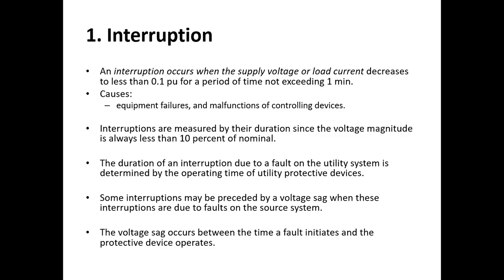Now the interruption. An interruption occurs when the supply voltage or load current decreases to less than 0.1 per unit for a period of time not exceeding 1 minute. So it is a complete loss of supply voltage. Interruptions are measured by their duration, since the voltage magnitude is always less than 10% of nominal. The duration of an interruption due to a fault on the utility system is determined by the operating time of the utility protective devices. Some interruptions may be preceded by a voltage sag. When these interruptions are due to faults on the source system, the voltage sag occurs between the time a fault is initiated and a protective device operates.